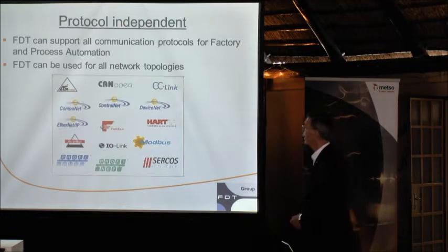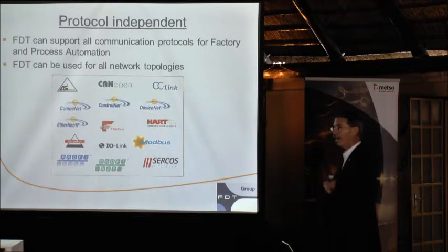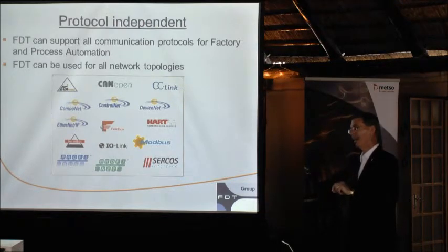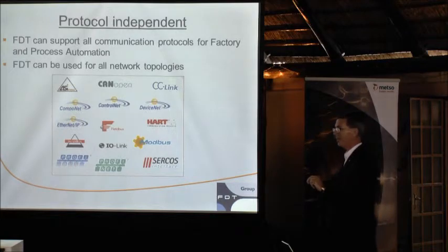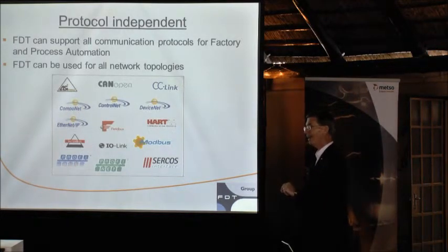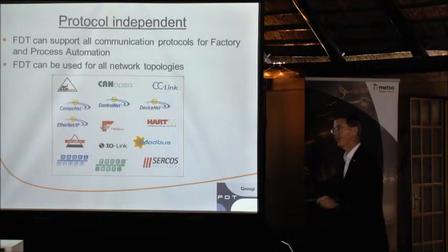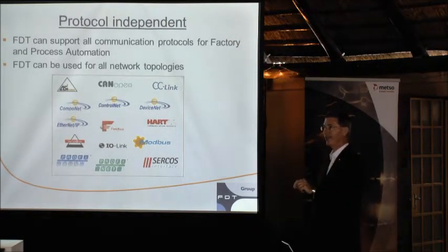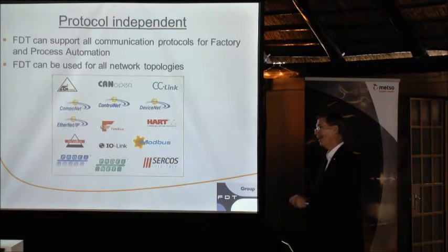On the communication side, there are DTMs that control communications. Our job is to make sure every network on the market is compatible with the standard. The engineers who conceived the standard realized this would be an ongoing battle, since there would always be another network coming out or changes to existing network standards. So they didn't want us to have to re-release the FDT standard every time a new network appeared, or when someone added wireless to a previously wired-only network. Instead, the architecture allows us to add a network at any time just by releasing an annex that deals with that particular network, and all existing applications can immediately take advantage of it.